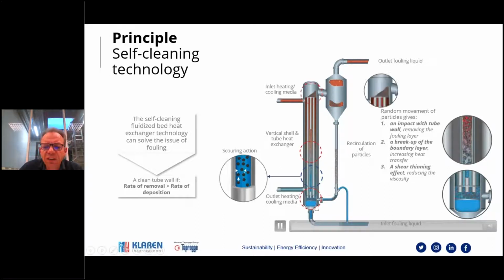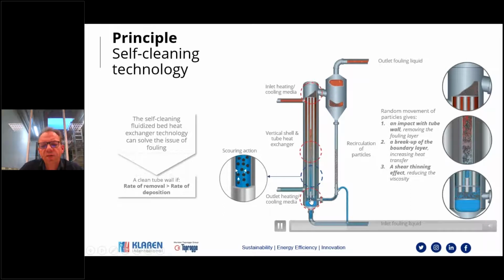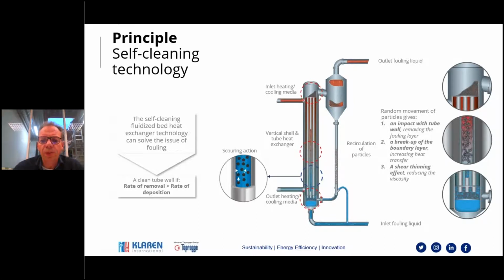Second point to emphasize is that where we feed particles to the heat exchanger, what we call the inlet channel, is a really important part, because you can imagine if you want to distribute particles over 563 tubes, then it's a lot more complicated than if you need to do that over 5. So core of our technology is that we know how to design this inlet channel in order to make sure that all tubes have an equal amount of cleaning particles.